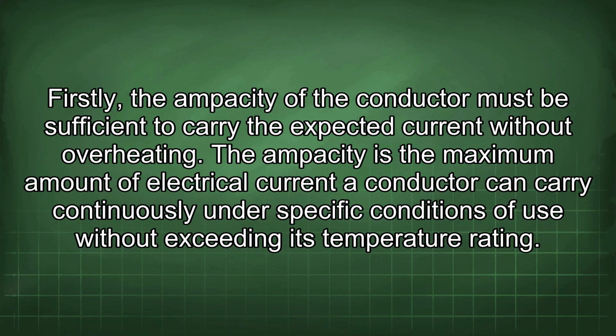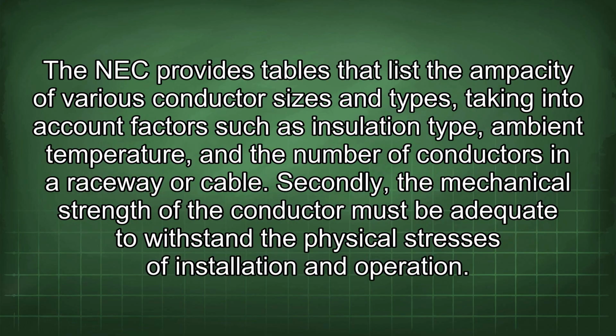Firstly, the ampacity of the conductor must be sufficient to carry the expected current without overheating. The ampacity is the maximum amount of electrical current a conductor can carry continuously under specific conditions of use without exceeding its temperature rating. The NEC provides tables that list the ampacity of various conductor sizes and types, taking into account factors such as insulation type, ambient temperature, and the number of conductors in a raceway or cable.